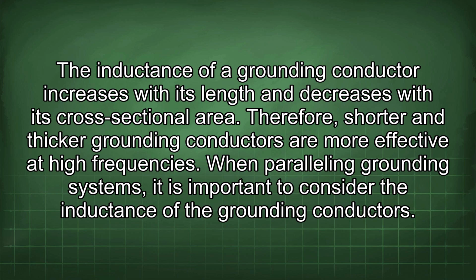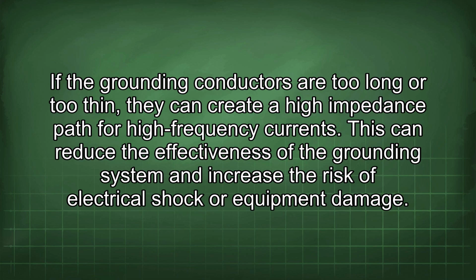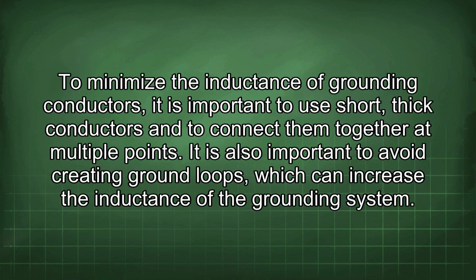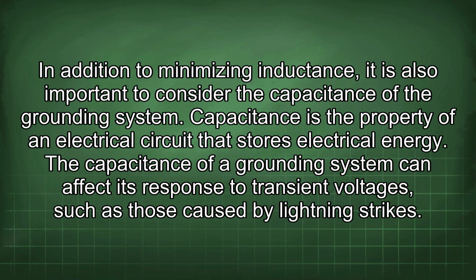When paralleling grounding systems, it is important to consider the inductance of the grounding conductors. If the grounding conductors are too long or too thin, they can create a high impedance path for high-frequency currents. This can reduce the effectiveness of the grounding system and increase the risk of electrical shock or equipment damage. To minimize the inductance of grounding conductors, it is important to use short, thick conductors and to connect them together at multiple points. It is also important to avoid creating ground loops, which can increase the inductance of the grounding system. In addition to minimizing inductance, it is also important to consider the capacitance of the grounding system.